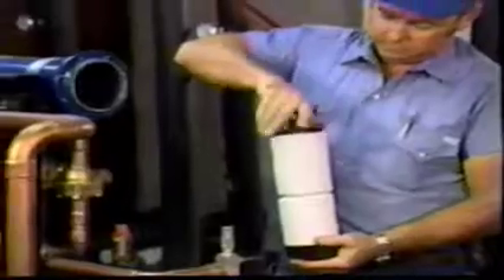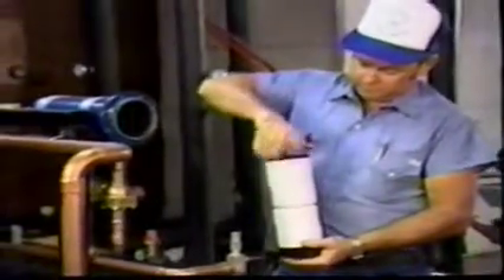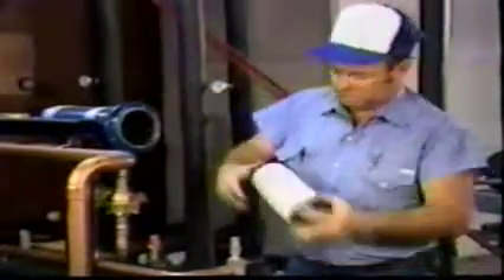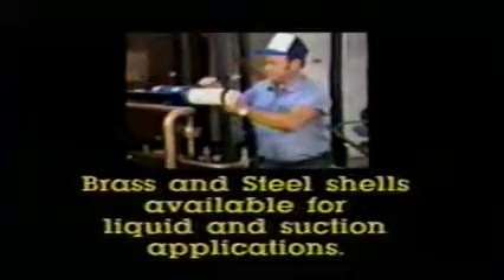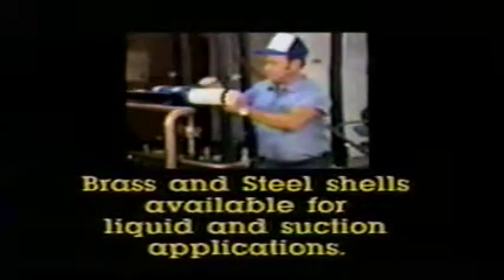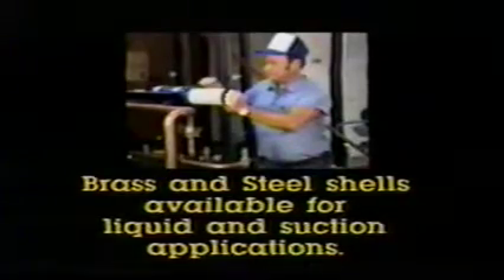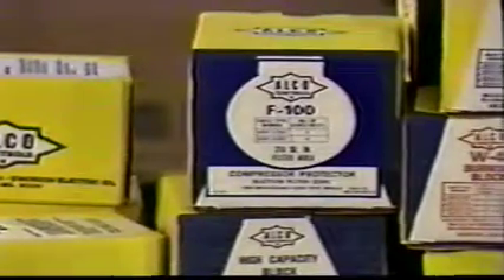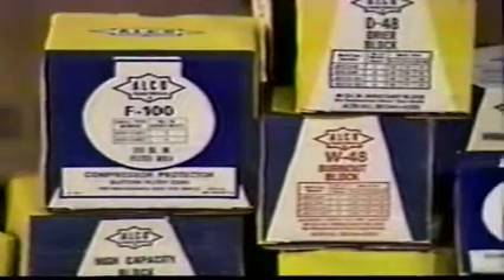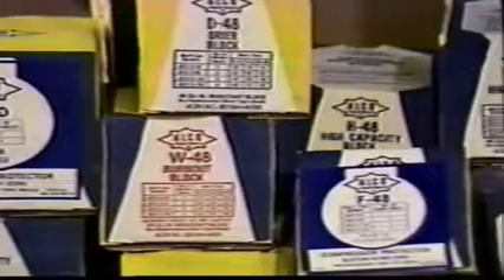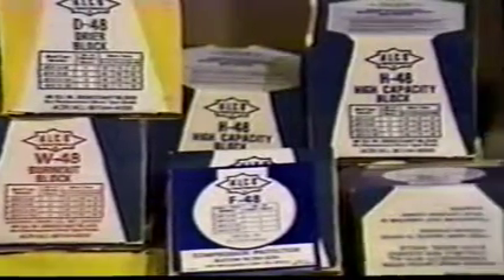One last option remaining in the selection process for filter dryers is the choice between standard sealed filter dryers and replaceable element filter dryers. The replaceable elements provide higher flow capacities and are typically used on larger air conditioning and refrigeration systems. Elements are available that provide for specialized filtering, drying, and acid removal jobs. Special burnout blocks are also available. Standard blocks provide system protection from water and acids in most general-purpose applications.